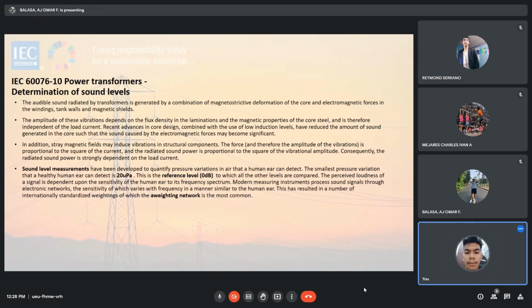Recent advances in core design, combined with the use of low induction levels, have reduced the amount of sound generated in the core such that the sound caused by electromagnetic forces may become significant. In addition, stray magnetic fields may increase vibrations in structural components. The force, and therefore the amplitude of the vibration, is proportional to the square of the current, and the radiated sound power is proportional to the square of the vibrational amplitude. Consequently, the radiated sound power is strongly dependent on the load current.